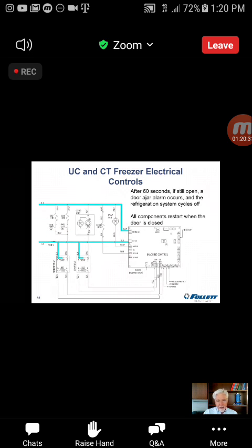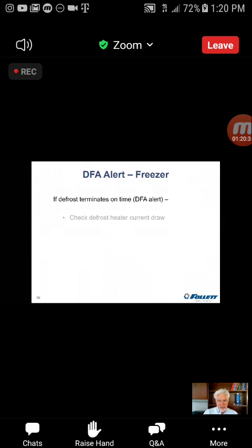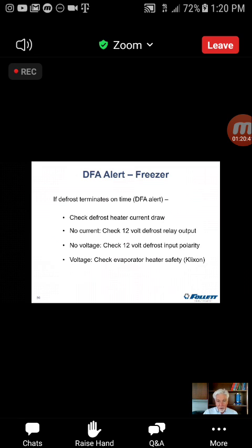Now, they open at a ridiculously high temperature. It's like 70 or 80 degrees. So obviously, they should never open. If they open, you've got some real problems. They're there as a safety. UL requires this. So if that relay gets stuck closed, we don't turn this thing into an oven. All right, so that's their purpose. They really do nothing more than that.